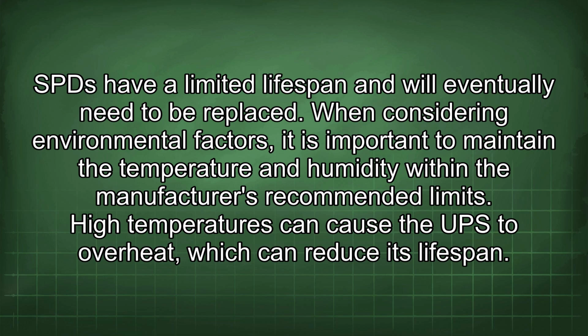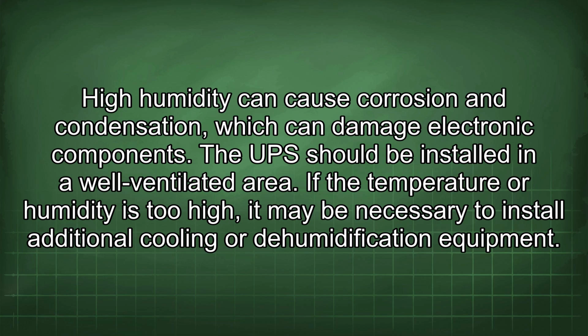When considering environmental factors, it is important to maintain the temperature and humidity within the manufacturer's recommended limits. High temperatures can cause the UPS to overheat, which can reduce its lifespan. High humidity can cause corrosion and condensation, which can damage electronic components. The UPS should be installed in a well-ventilated area. If the temperature or humidity is too high, it may be necessary to install additional cooling or dehumidification equipment.